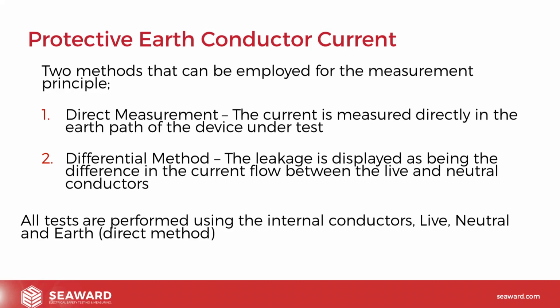Now those secondary paths could be flowing away from the device and therefore not being picked up by the tester, which could give you an inaccurate reading. So as I said, with the direct method, we simply power the equipment up, live and neutral are flowing through the device, it is active, and the test equipment is measuring any current that is flowing back into the instrument via the earth cable. The alternate method for this is what we call the differential method.